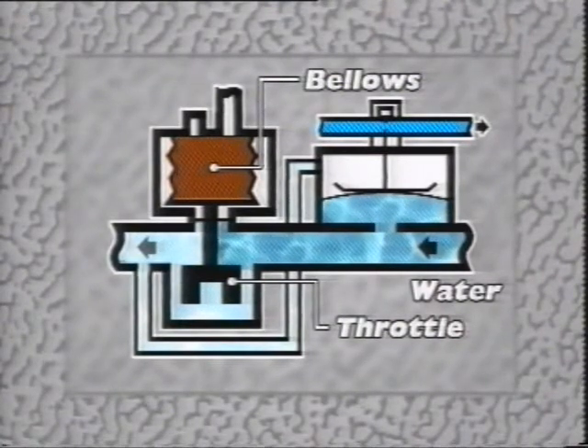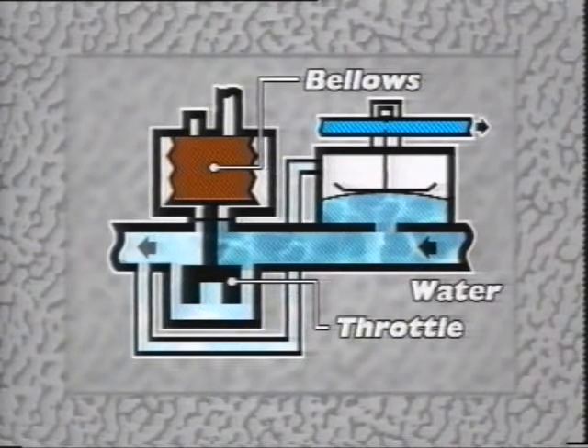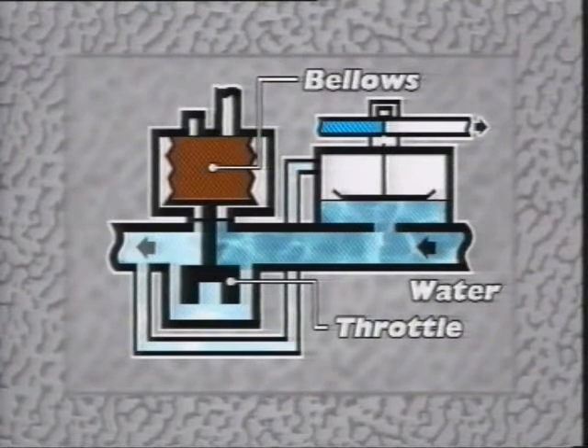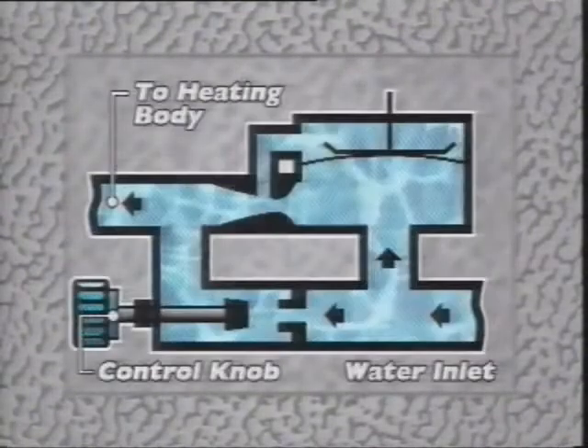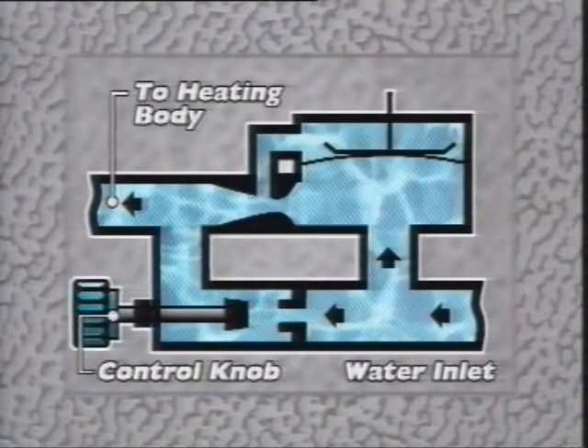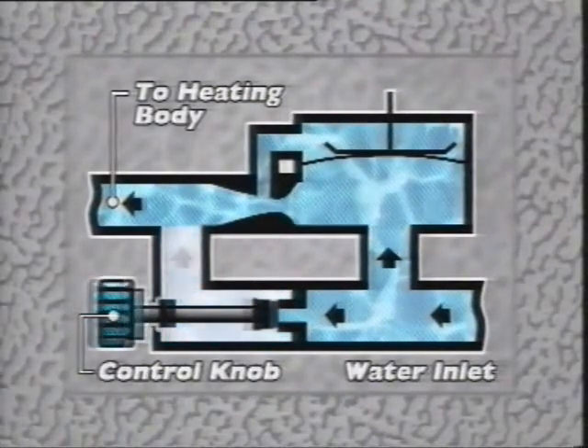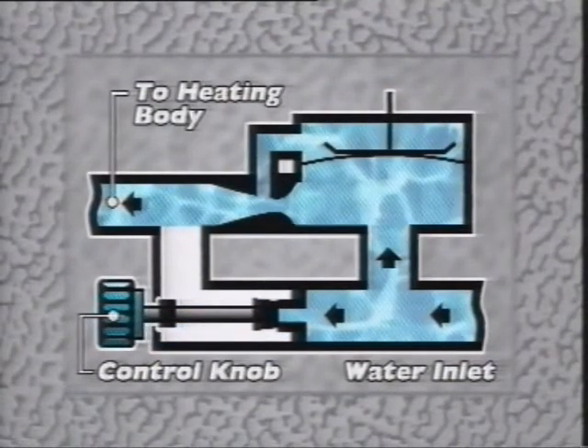If the water flow dropped too much, the heat exchanger might overheat. So, to prevent that, the throttle assembly is connected to the automatic valve of the water section through this small pipe. This means that it acts as a venturi. If the flow rate through the heater gets too low, the differential pressure in the heater's automatic valve section will equalize, and the gas flow to the burner will be shut off. This is a simpler method. It's a temperature selector which is simply a screw in the throttle which alters the water flow rate and so changes the water temperature.